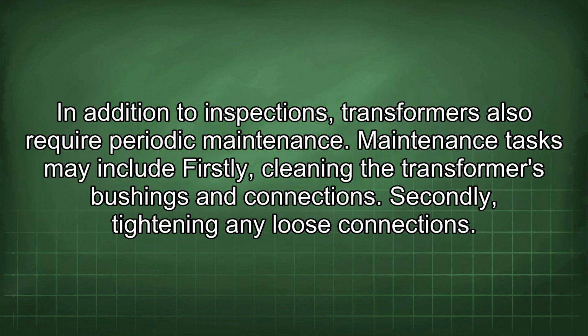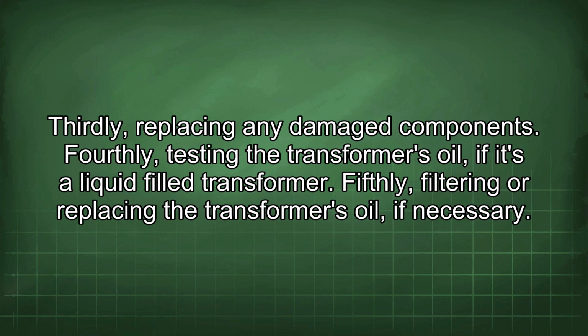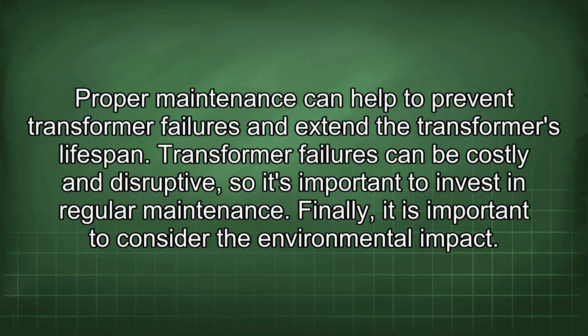In addition to inspections, transformers also require periodic maintenance. Maintenance tasks may include, firstly, cleaning the transformer's bushings and connections. Secondly, tightening any loose connections. Thirdly, replacing any damaged components. Fourthly, testing the transformer's oil, if it's a liquid-filled transformer. Fifthly, filtering or replacing the transformer's oil, if necessary. Proper maintenance can help to prevent transformer failures and extend the transformer's lifespan. Transformer failures can be costly and disruptive, so it's important to invest in regular maintenance.